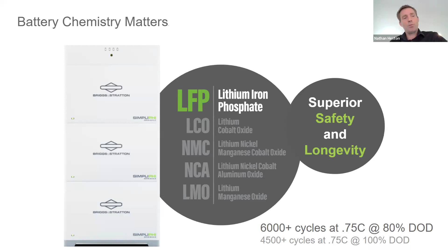So these batteries can come in single stacks, double stacks, triple stacks. Each stack does have to have a stack controller on the top of it, and that's where the communicating equipment will be connected to go out to the inverter or the charge controller.